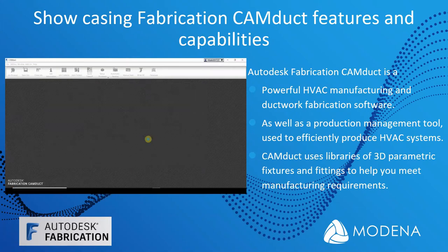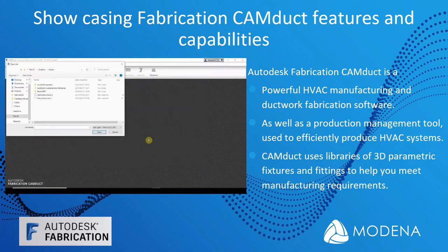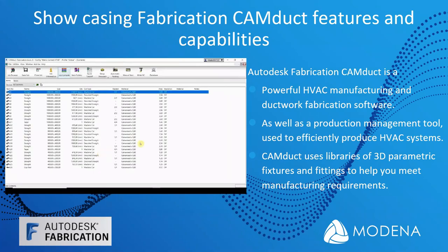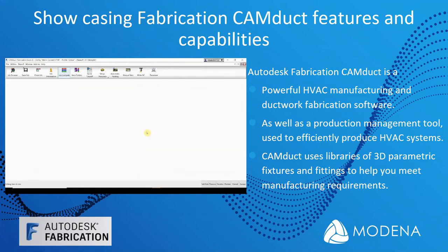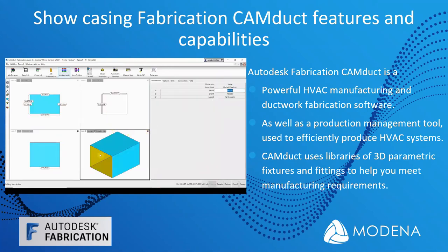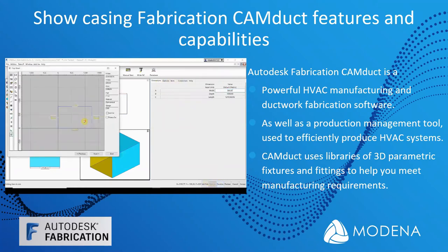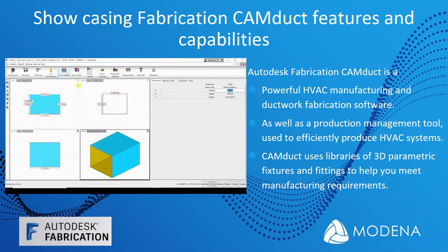So we start off with the file that we've actually brought out from CADmep. We're going to open that MAJ file. As you can see, it's opened. Here are the pieces from A1 to A26. I'm going to go ahead and show you guys what actually happens there. So now here is the actual duct piece. I can basically show you the details. I can develop it. Let me show you how to actually develop it. I've developed it there, and you can see what it's going to look like when it's being cut.